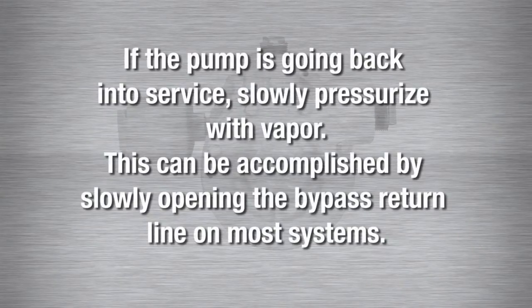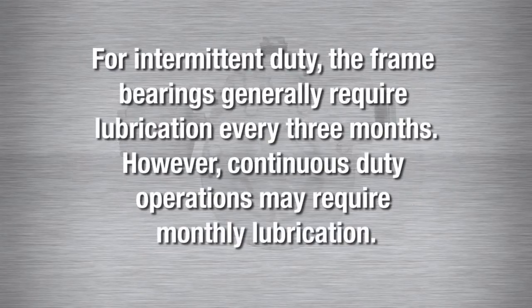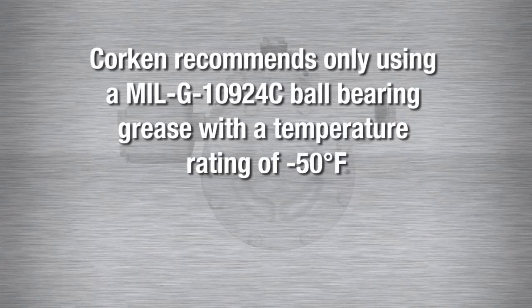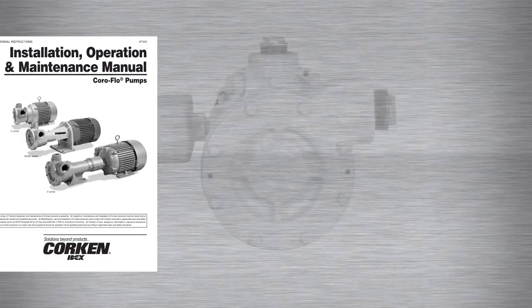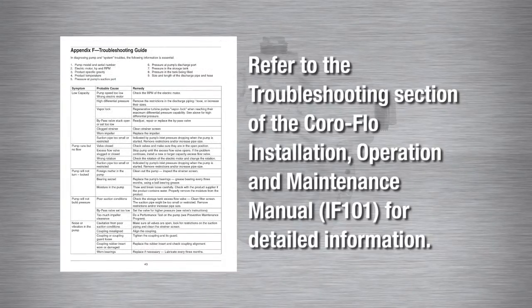If the pump is going back into service, slowly pressurize with vapor. This can be accomplished by slowly opening the bypass return line on most systems. If the pump is placed into short or long-term storage, close all openings and partially fill the pump with some light oil to protect against rust and corrosion. For intermittent duty, the frame bearings generally require lubrication every three months. However, continuous duty operations may require monthly lubrication. Corken recommends only using a MIL-G-10924C ball bearing grease with a temperature rating of negative 50 degrees Fahrenheit. Please refer to the troubleshooting section of the Coro-Flo Installation, Operation and Maintenance Manual, item number IF101, for detailed information. This manual may be downloaded from the literature section of our website at corken.com.